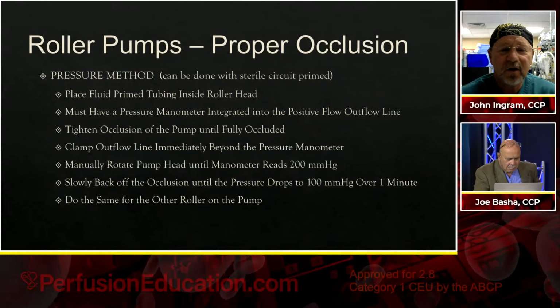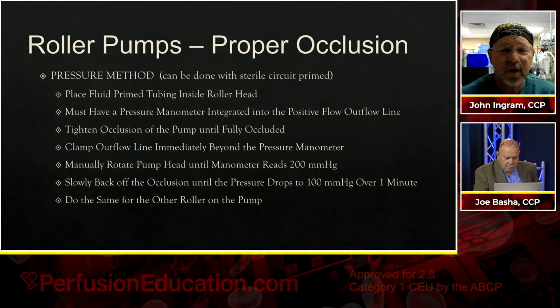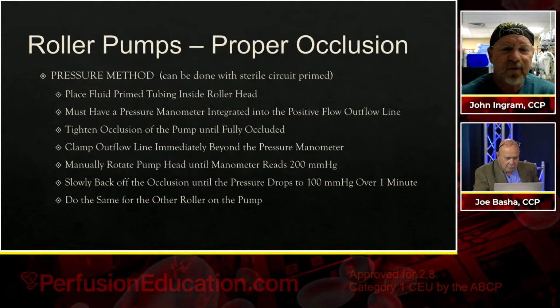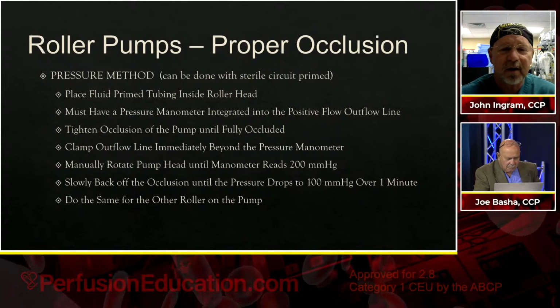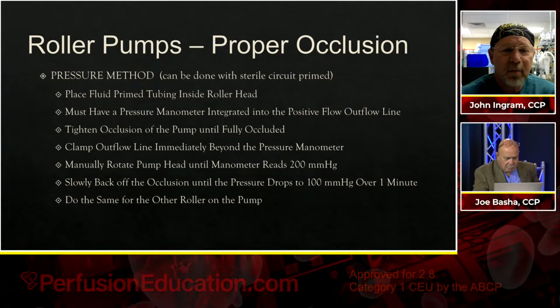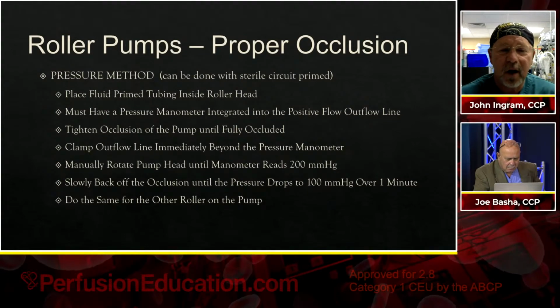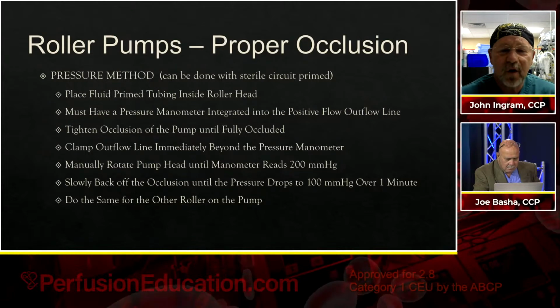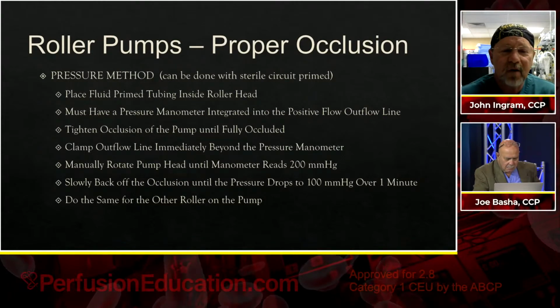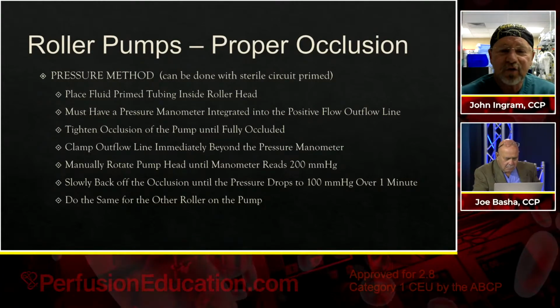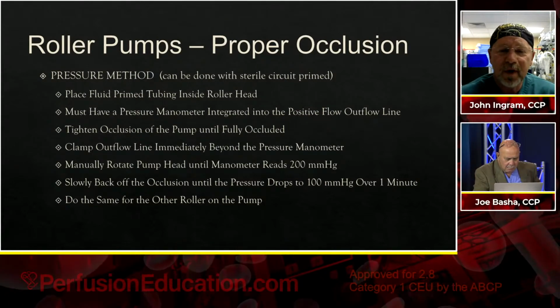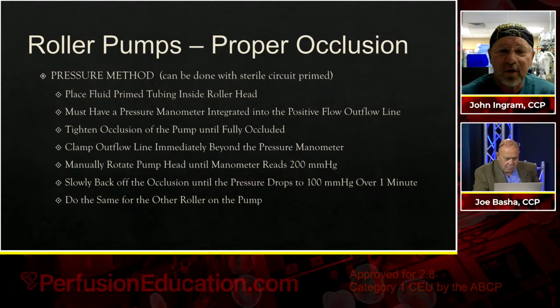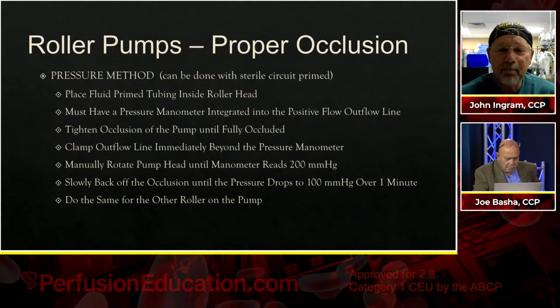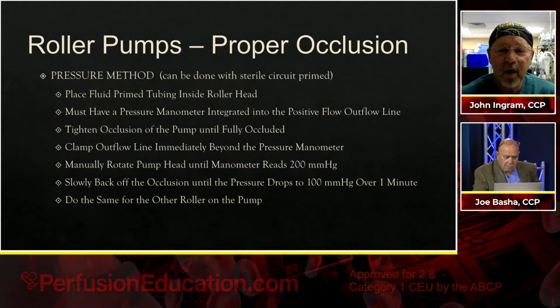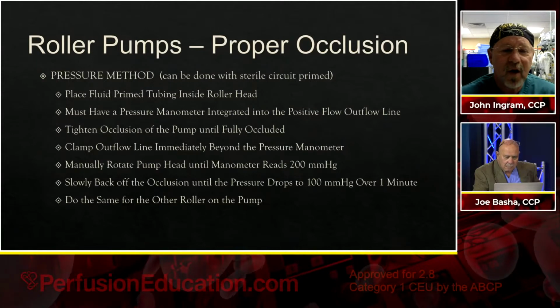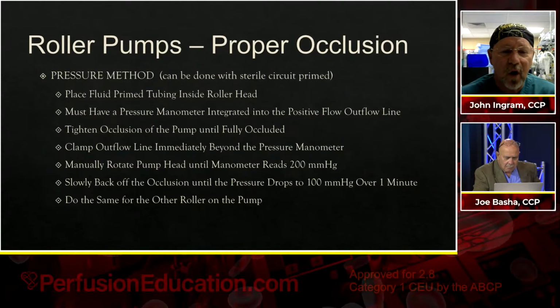You then tighten the occlusion of the pump pretty much until it's fully occluded, and then you clamp your outflow line somewhere just beyond the pressure manometer. Then you manually rotate your pump head until the manometer goes up and reads 200 millimeters of mercury. Slowly back off of the occlusion until the pressure drops slowly over a 1 minute period down to 100 millimeters of mercury. So it should take about a minute for it to drop from 200 to 100. And then you have to do the same for the other roller on that same pump.